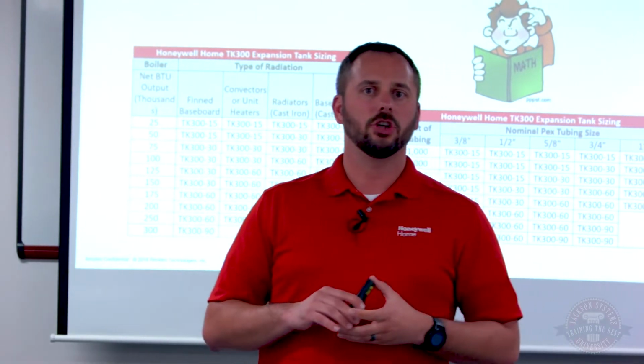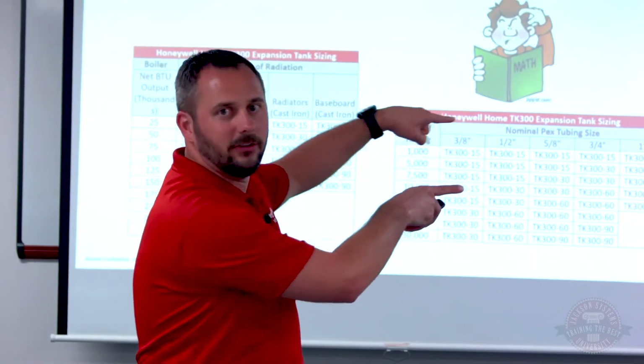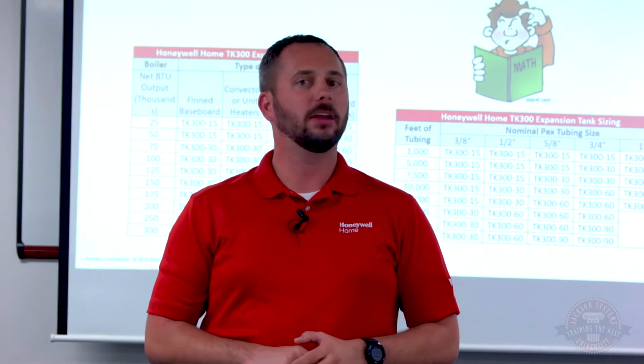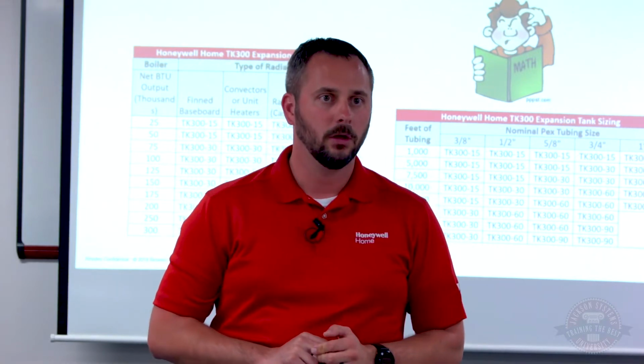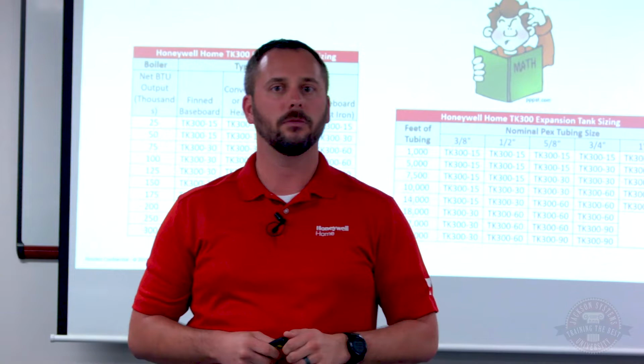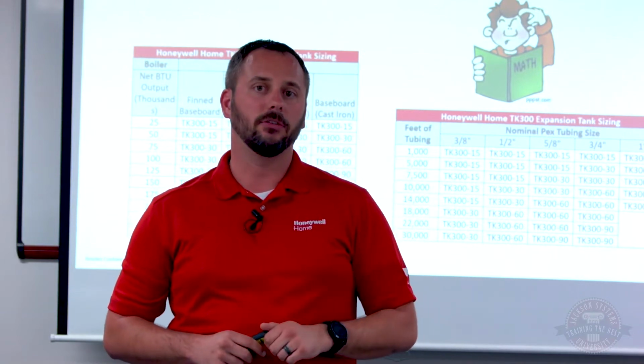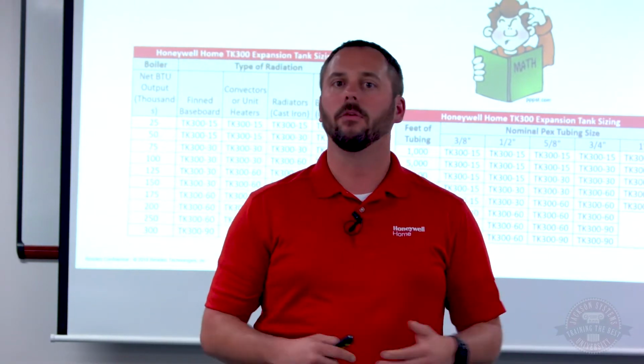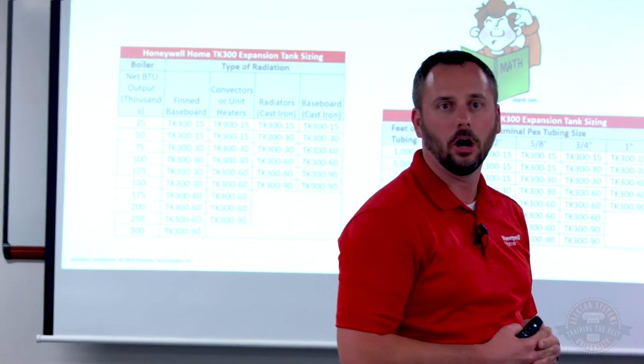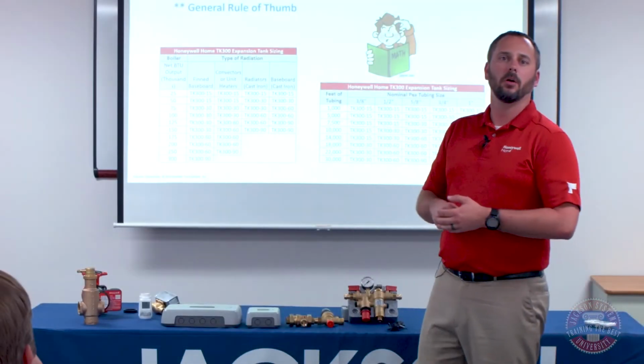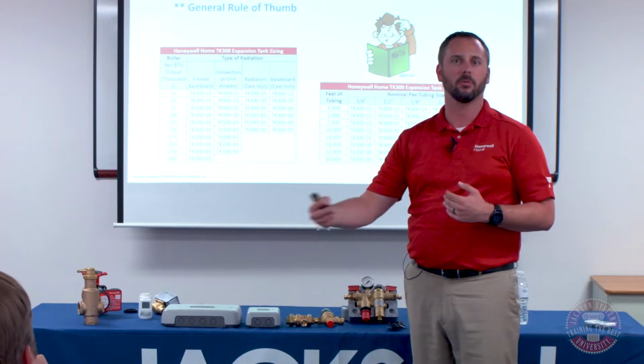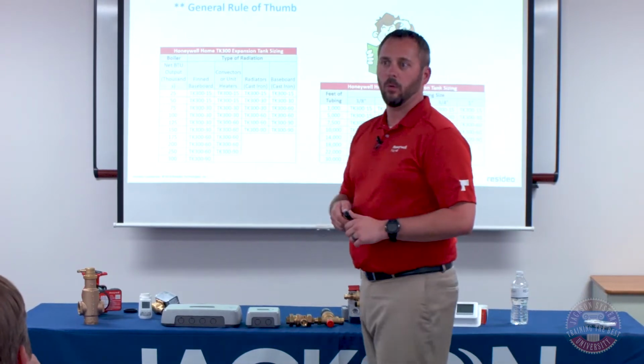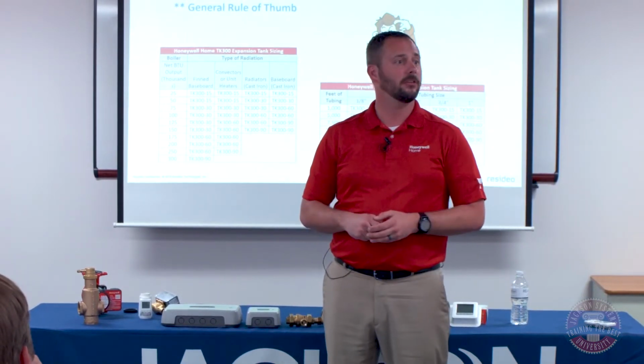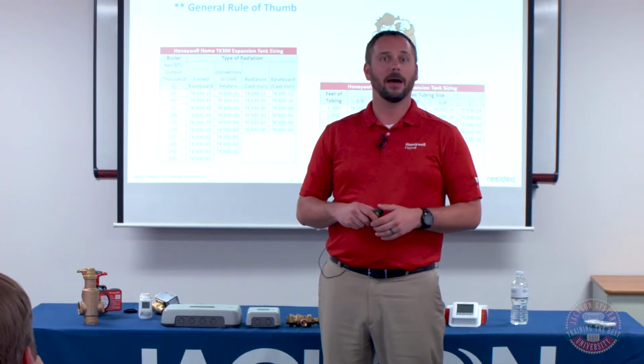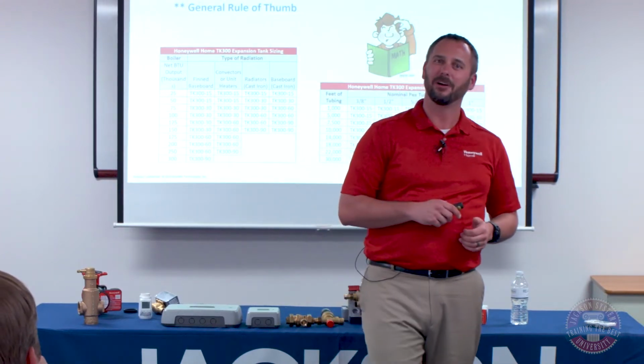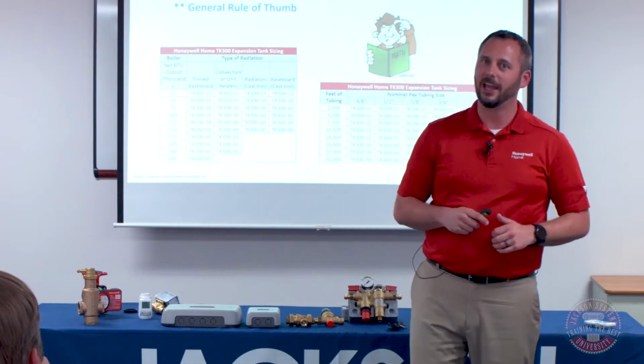I've also got another chart to the right that shows you what you can use based on estimations of PEX tubing. So both of these charts can be used if you don't want to add it up, but my advice is always to add up the water volume, at least to get a rough gauge of where you are, because that'll let you know whether you're close to the size and whether you should go up to the next one. We also have expansion tanks. If it's a commercial job, it adds about $1,000 right off the top to the price. But if you need commercial expansion tanks, we have those as well.